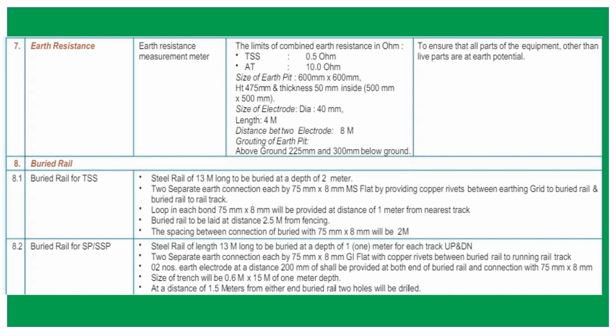And the bond must be looped from the track 1 meter away. There will be a loop to give flexibility, otherwise it will cut. If it is straight, the possibility is it may cut. This loop gives spring action. So buried rail should be 2.5 meter from the fencing, and the spacing between connections of buried rail with 75 into 8 millimeter flat will be 2 meter. Sorry, 2 meter, not 1.5, 2 meter. And it will also be connected with the power transformer earthing leg and with the earthing mesh. All connection will be with 75 into 8 millimeter MS flat.